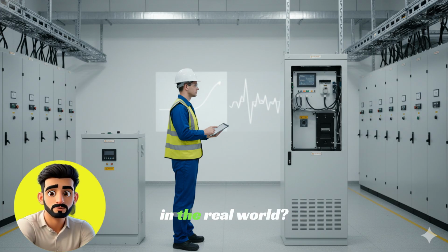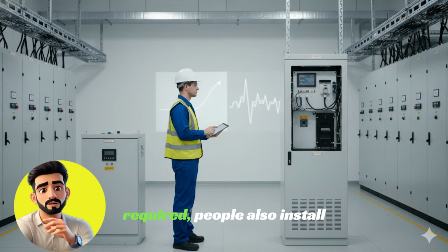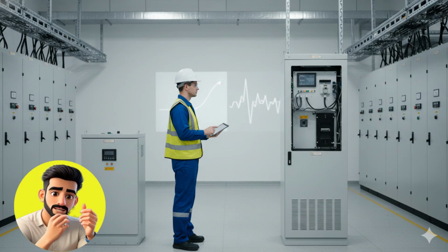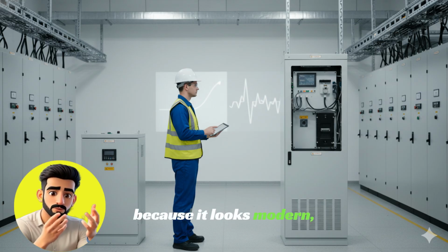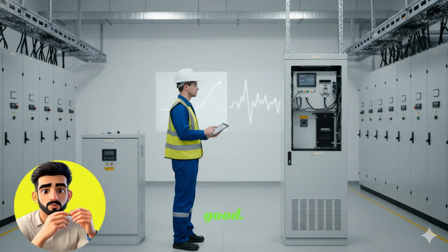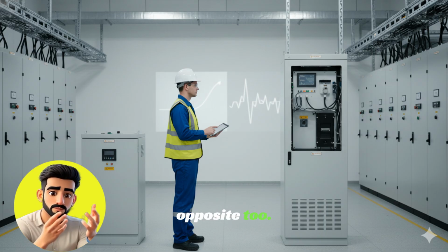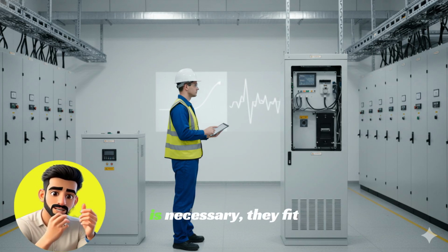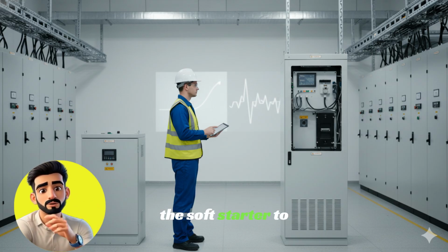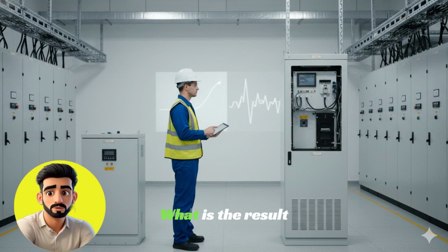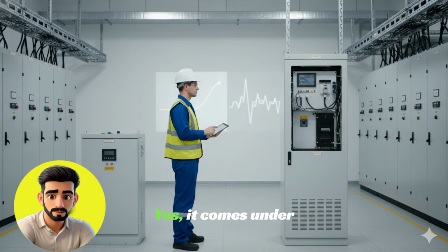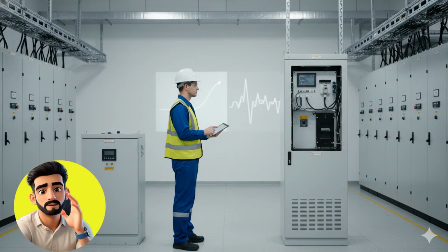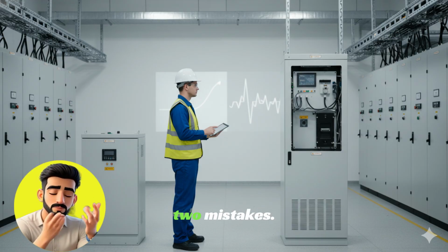What is the problem in the real world? In many plants where only smooth start is required, people also install VSD just because it looks modern or shiny equipment looks good. And it is the opposite too. Where precise speed control is necessary, they fit the soft starter to save costs. What is the result of this? Either over-engineering occurs, or the process comes under protection. Today we will learn how to avoid these two mistakes.